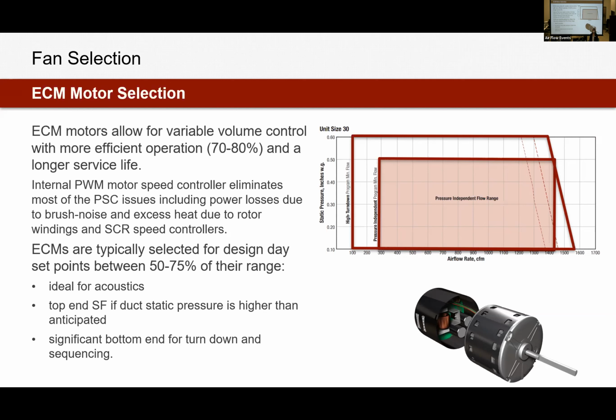In the worst case scenario, can you go all the way up to 0.6 inches in static pressure with the high turn down? With high turn down, yes. Anything above 0.6, the fan curve starts to level out really quick. So 0.6 is your safe end. And then if you need to go above that, we start looking at lab data.